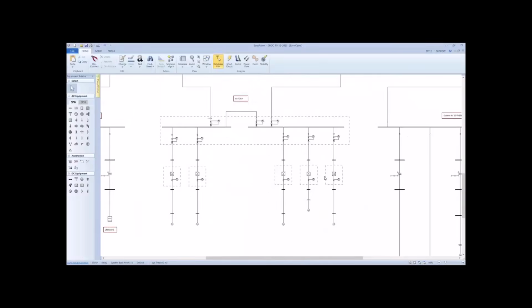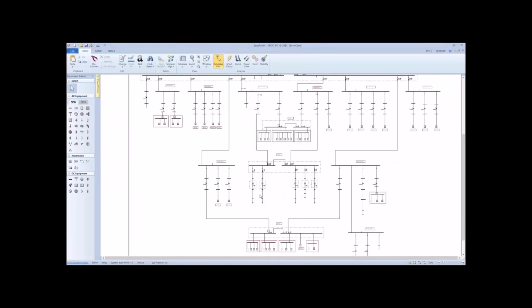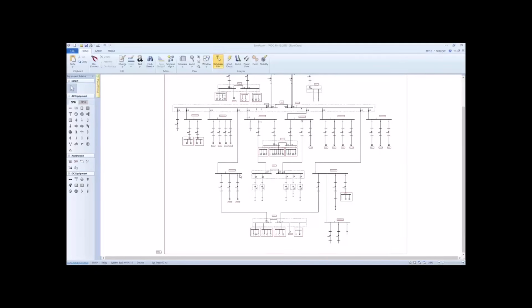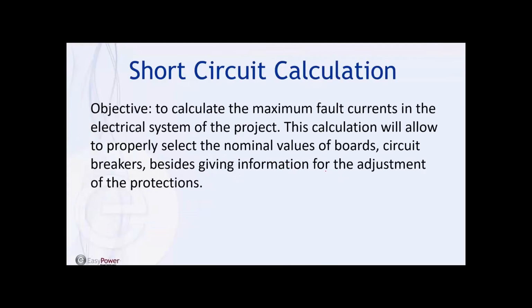So basically that's the general settings in EasyPower. Let's come back to the presentation — we'll talk about the short circuit calculation. Basically in this project, like in others, our objective is to calculate the maximum fault current in the electrical system or power system. With that calculation we can properly select the nominal values of panels, switchgears, MCCs, breakers, right? This kind of study is very common in most projects, and with that information we can also work on relay coordination.